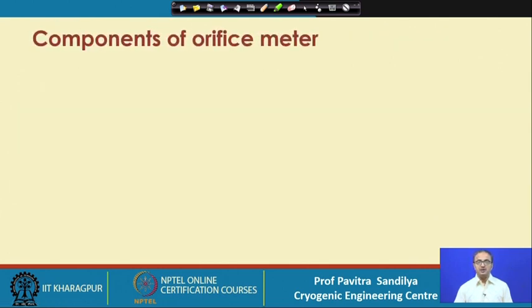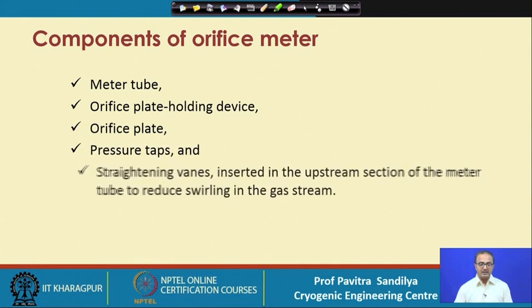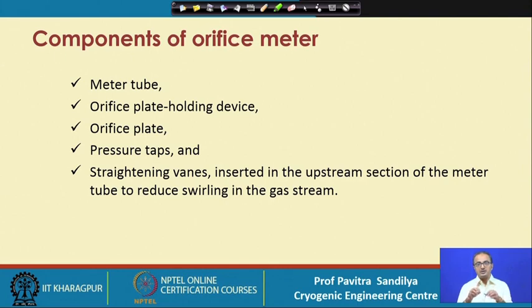The various components of the orifice meter are: the meter tube, the orifice plate holding device, the orifice plate, pressure taps, and the straightening vanes. These straightening vanes are inserted on the upstream side of the meter to reduce the swirling action in the gas stream, because swirls cause a lot of energy loss.